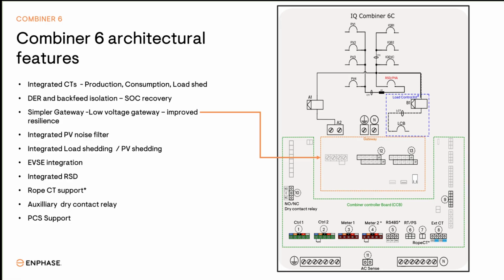The Combiner 6C also has a built-in ferrite core noise filter in the PV circuit path to reduce extraneous noise that may be injected from the home back to the Combiner 6C. This aids to increase the reliability and stability of power line communications between the microinverters and the gateway. As mentioned, an integrated load controller is built into the Combiner 6C and is able to shed up to 80 amps of single or combined loads.